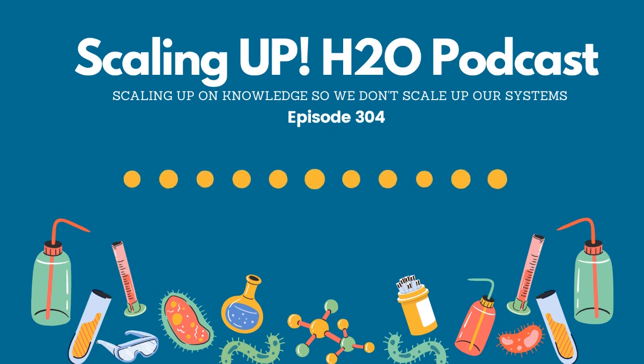And typically there is a reason for pitting. It might be how the coupon has been installed. It could be a flow issue. It could be a water treatment issue. But pitting is a sign that something is going on in the system. And I want to make sure that the Scaling Up Nation realizes that even though you might get back a report that says a corrosion coupon is good or better, it is never good or better if it has a pit in it. A pit is always a fail.